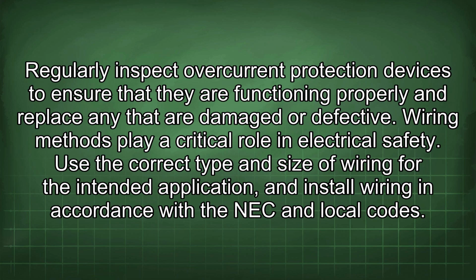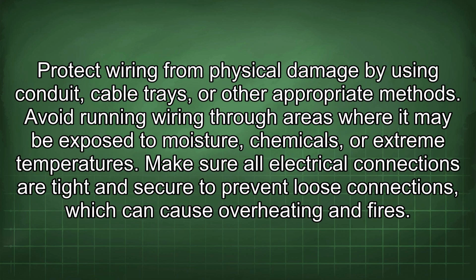Use the correct type and size of wiring for the intended application and install wiring in accordance with the NEC and local codes. Protect wiring from physical damage by using conduit, cable trays, or other appropriate methods. Avoid running wiring through areas where it may be exposed to moisture, chemicals, or extreme temperatures. Make sure all electrical connections are tight and secure to prevent loose connections, which can cause overheating and fires.